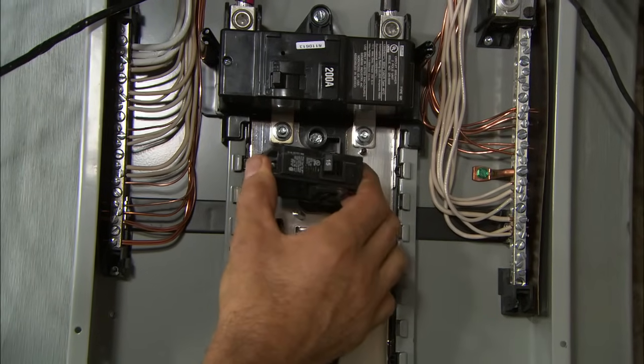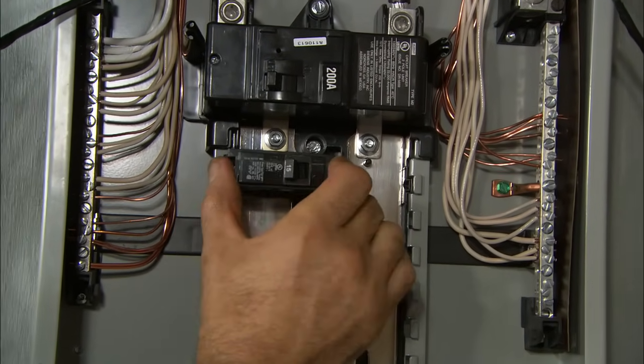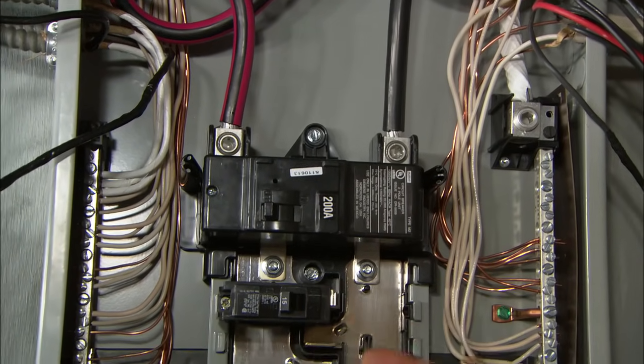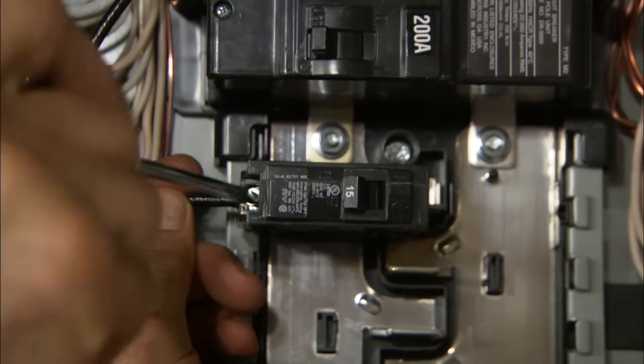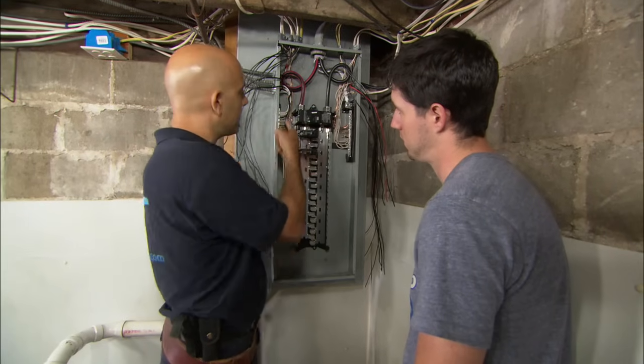The first circuit breaker I'm going to install is a 15 amp circuit breaker. When I plug it in, it's going to receive 120 volts from the left side of the bus bar. This wire here is a 15 amp wire — I'm going to go ahead and install it, tighten it down, and that's going to send power right up to that circuit.